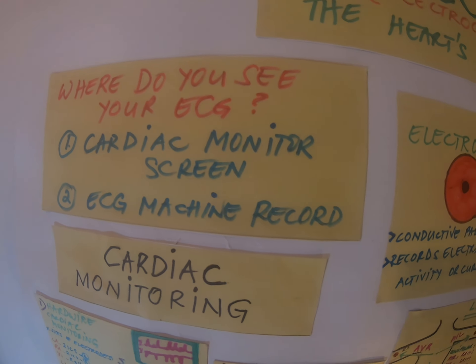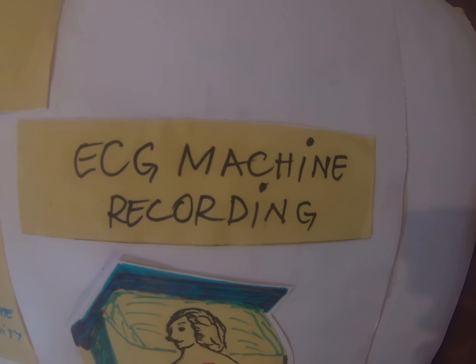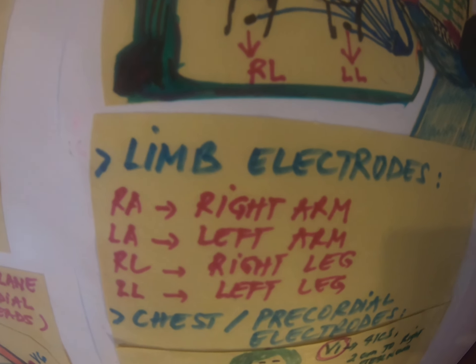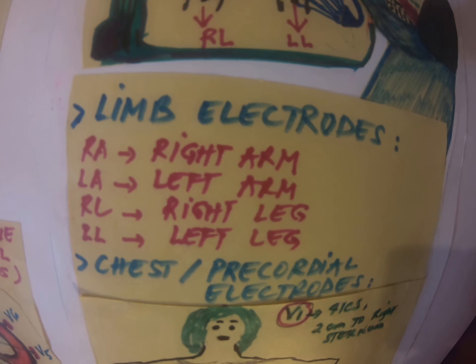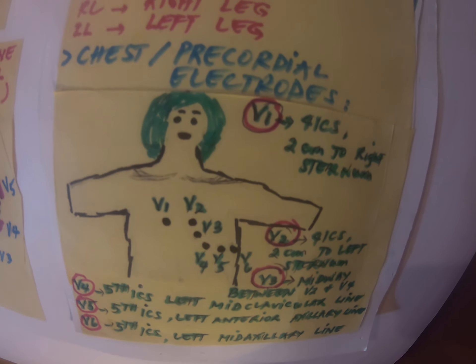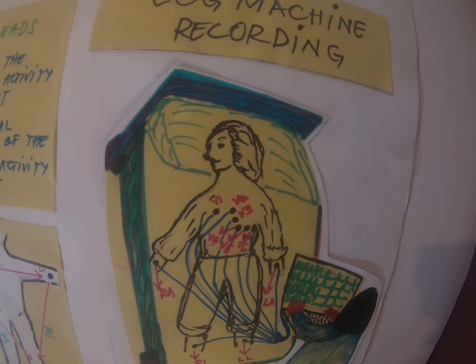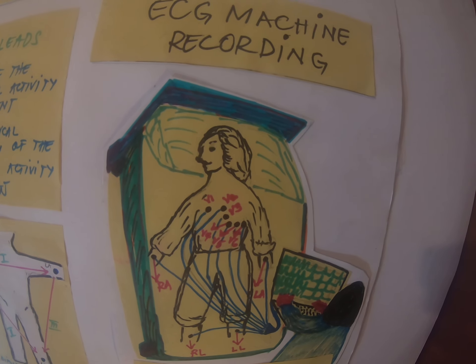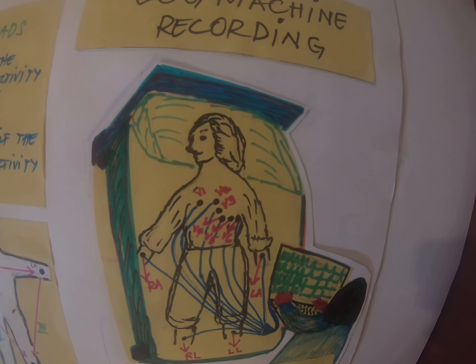The 12-lead ECG provides another view. The electrodes for the limb leads are applied on the right arm, left arm, right leg, and left leg. The chest electrodes go from V1 to V6. In total there are 12 leads but only 10 electrodes. All 12 leads are viewing the same electrical activity, but they are coming from different angles.